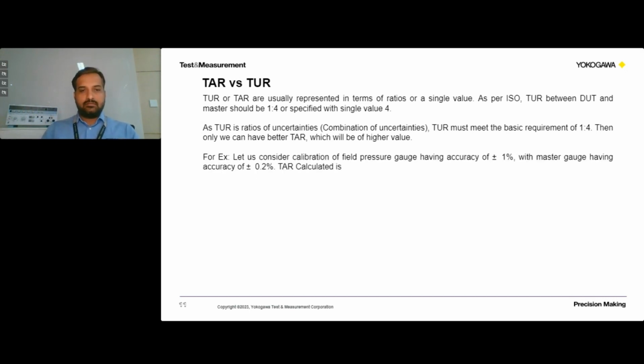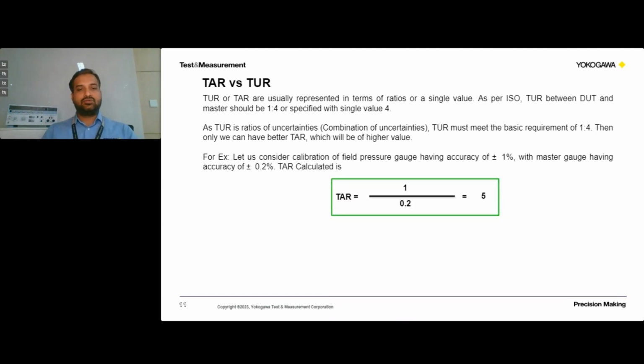And TUR must meet the basic requirement of 1:4. Then only we can have a better test accuracy ratio. For example, let us consider a pressure gauge which is having 1% of accuracy, and we will calibrate this pressure gauge with the master gauge, which is having 0.2 percentage of accuracy. So here, if we see the ratio, we are meeting the basic requirement of 4 times better. Means the 1:4 ratio we are just crossing, and the TAR we have got as full value of 5.